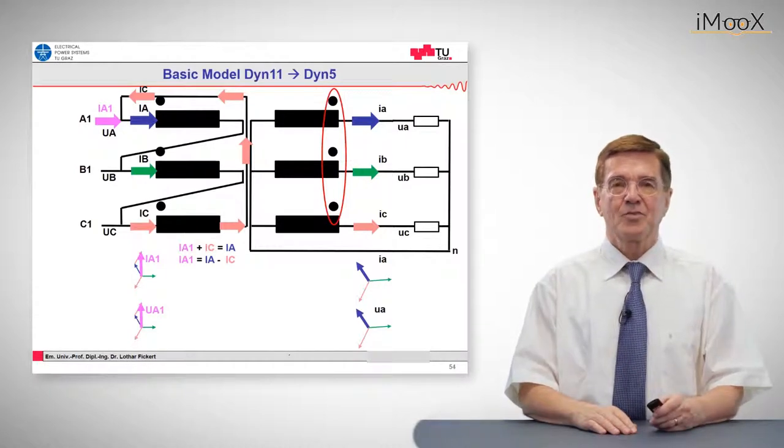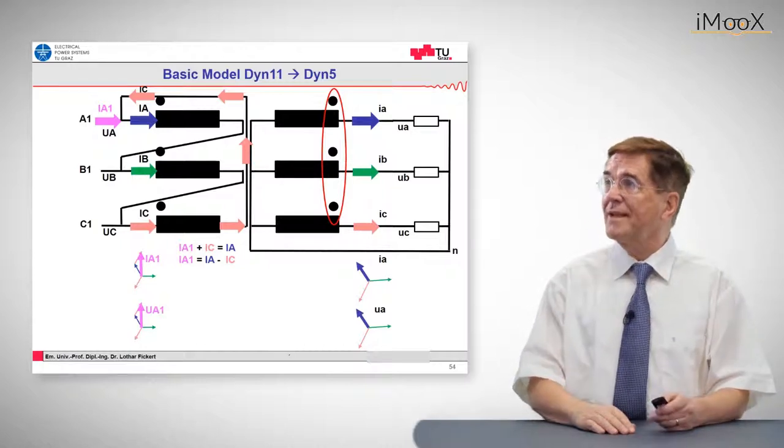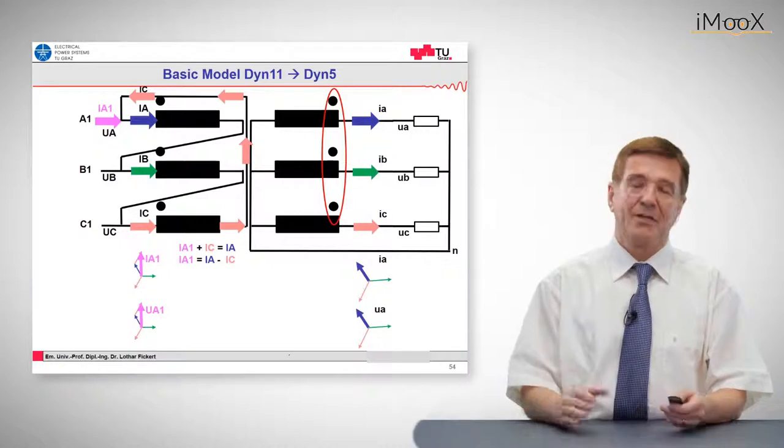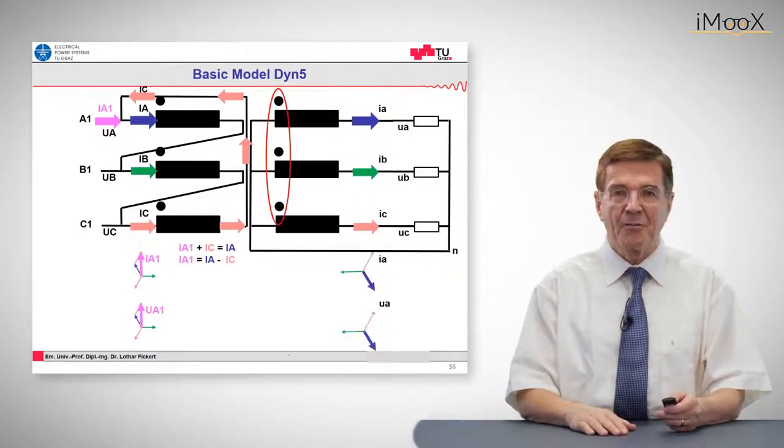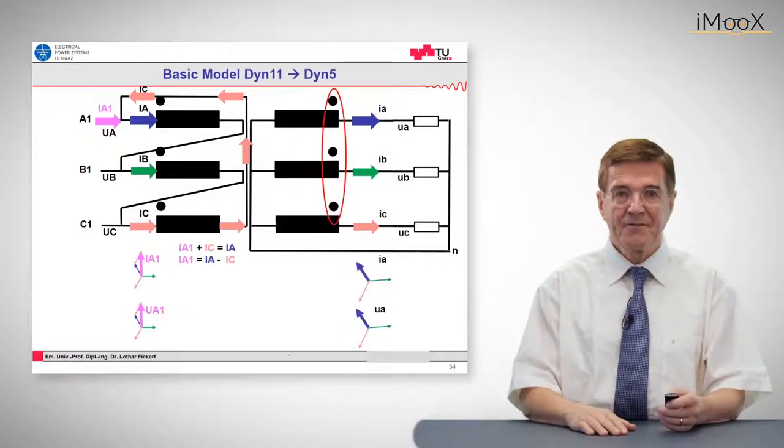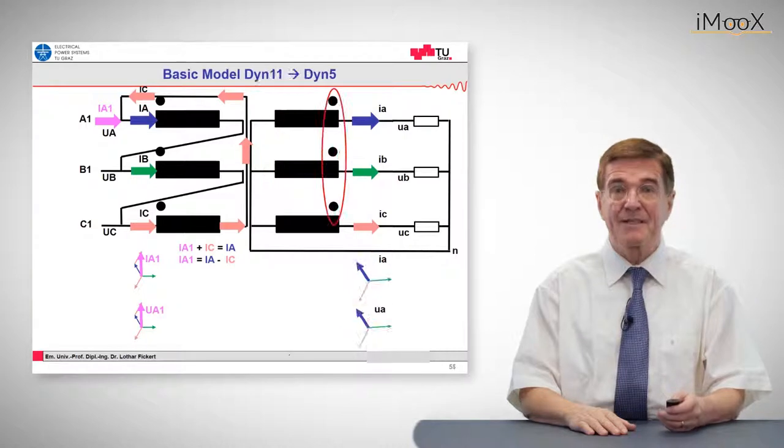Now the next one is the most usual one, that is Dy5. So again we have the previous one. And now we shift the polarization of the secondary winding in the opposite direction. You see, it was before. Now we have changed this and see what happens to the currents. The currents on the secondary side are turned by 180 degrees.